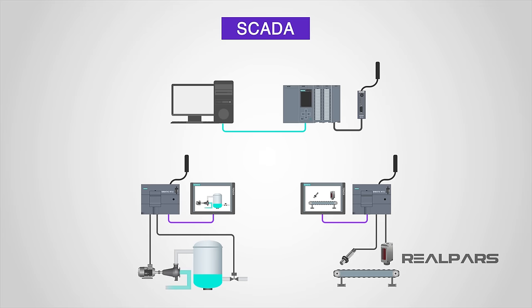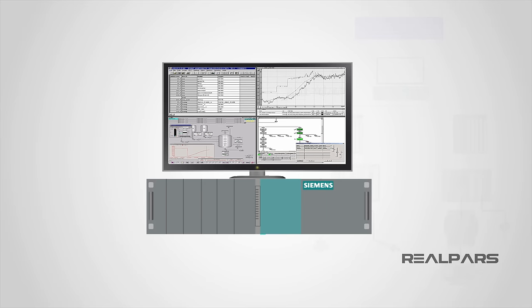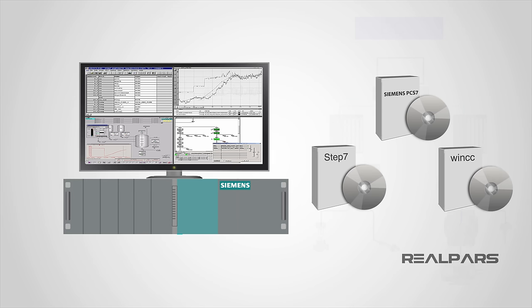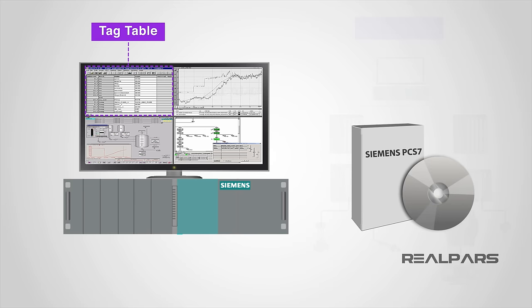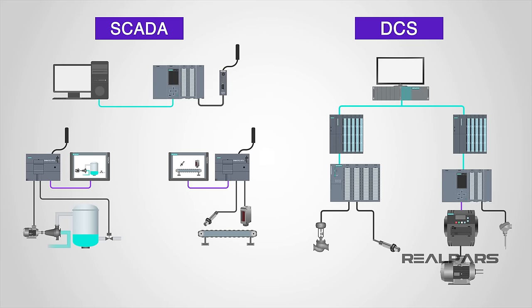While a SCADA system has HMIs or computers that are not necessarily of the same manufacturer, DCS systems have graphical interfaces that are typically integrated within the DCS system. This is a definite plus, as the requirement for additional software is not needed. As a bonus, the tags within the DCS are available for use without much additional effort. Clearly, the DCS has the advantage in this category.